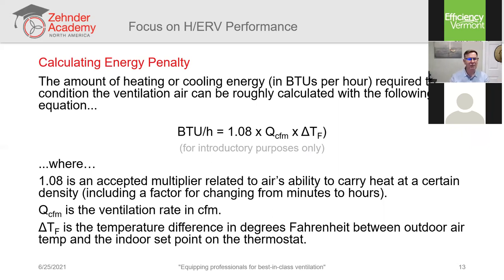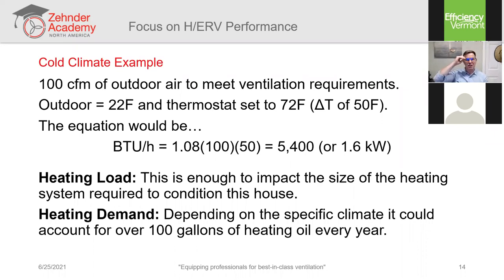Cold climate example: we want to ventilate with 100 CFM, outdoor temperature is 22°F, thermostat is set to 72°F — a ΔT of 50 degrees Fahrenheit. The equation gives us 1.08 × 100 × 50 = 5,400 BTUs per hour, or 1.6 kilowatts. In terms of heating load, this is enough to impact the size of the heating system required — 1.6 kilowatts could mean a different size heat pump.